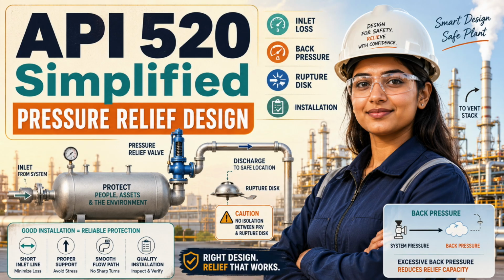Operating ratio matters as well. Different disc designs tolerate different relationships between normal operating pressure and marked burst pressure. Cyclic pressure, pulsation, vacuum, and pressure fluctuations can shorten life and cause premature failure. The real selection question is not only what burst pressure do I need, it is also how close will normal operation run to that pressure, and can this design survive the actual service?